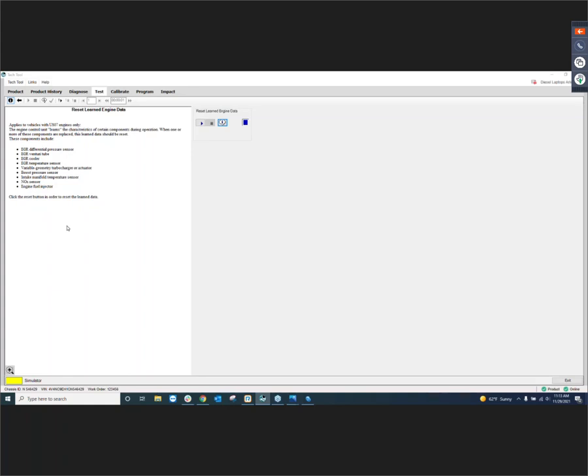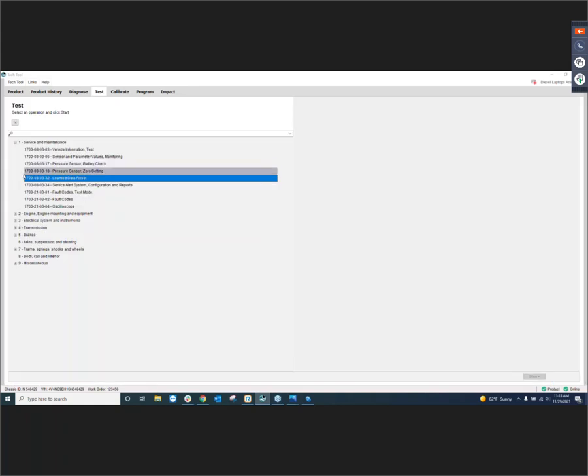What's going to happen is people will say, I don't like what I see from my NOx sensor. The system can only communicate in diagnostic troubleshooting language, so it'll throw you a code saying erratic data, valid, invalid, whatever. You'll go in thinking, I just changed the NOx sensor, what happened? Ultimately, you have to look at that and realize this is happening because you need to do a data reset after changing that sensor. That's just what it is. Save yourself a little bit of a headache.